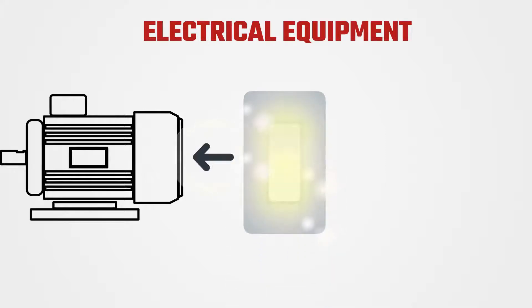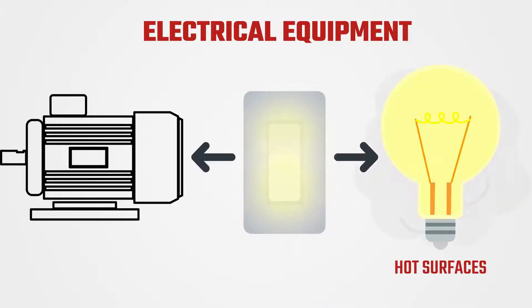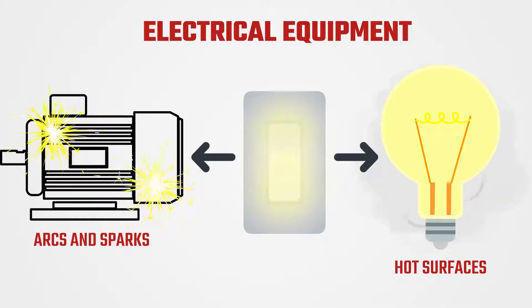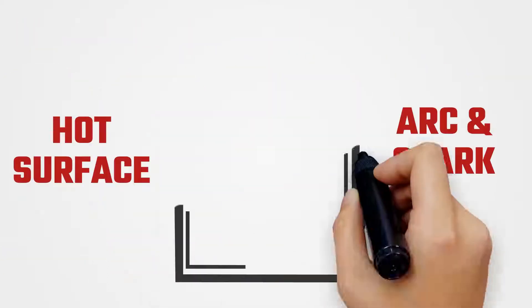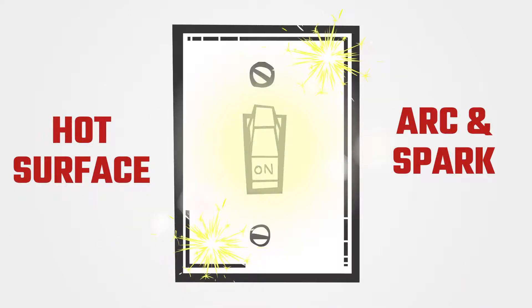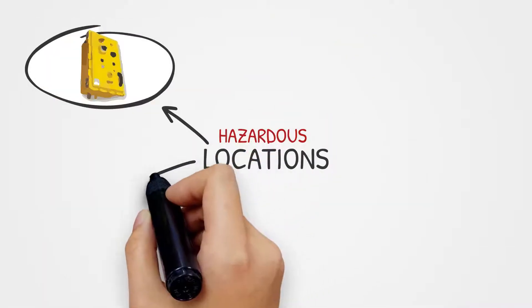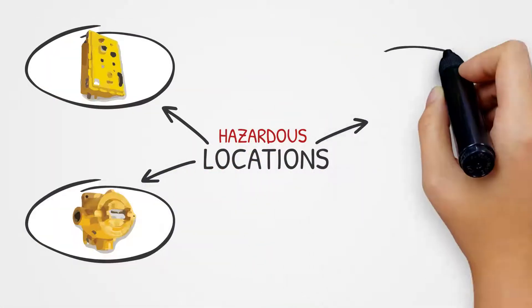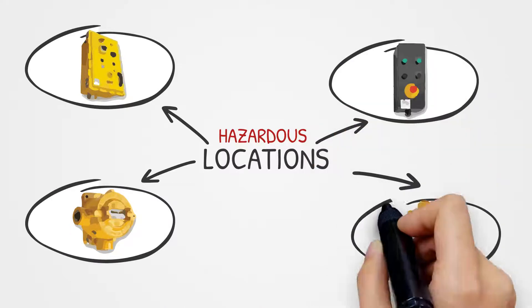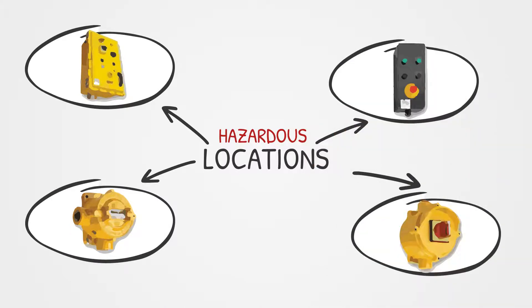Electrical equipment can provide an ignition source, because an electrical circuit can raise the temperature of equipment surfaces and also generate even brief, seemingly harmless arcs and sparks. In other words, two main sources of ignition from electrical equipment are hot surfaces and arcs and sparks. Even though electrical devices can create conditions that become explosive if all the required elements of the fire triangle are present, electrical equipment is still required, even in hazardous locations.